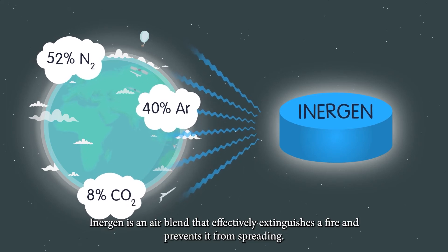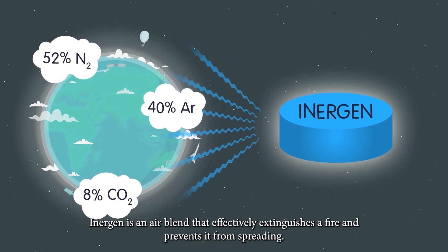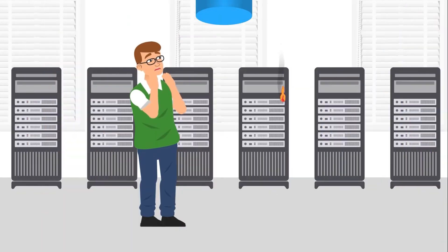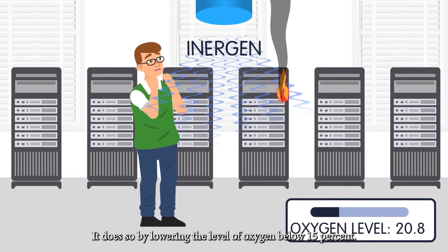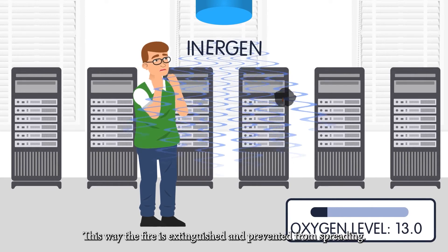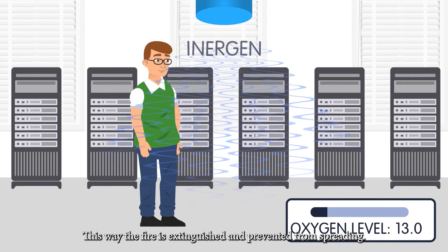Inergen is an air blend that effectively extinguishes a fire and prevents it from spreading. It does so by lowering the level of oxygen below 15%, so the fire is extinguished and prevented from spreading.